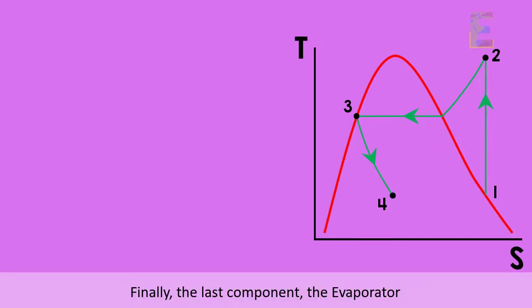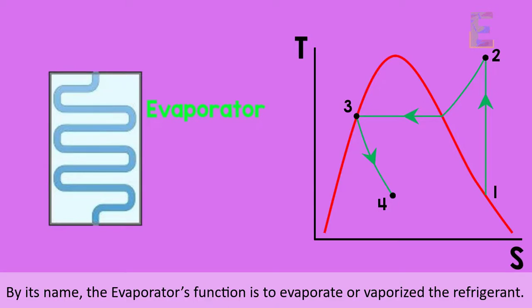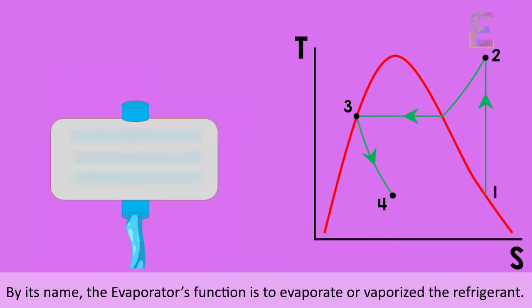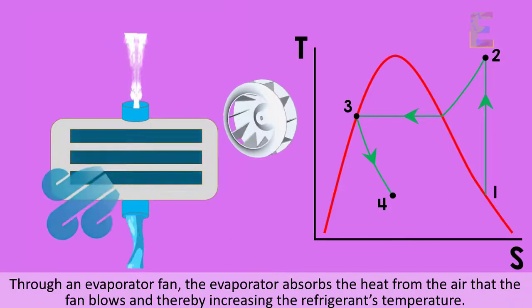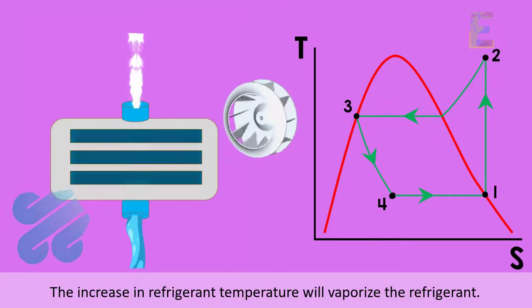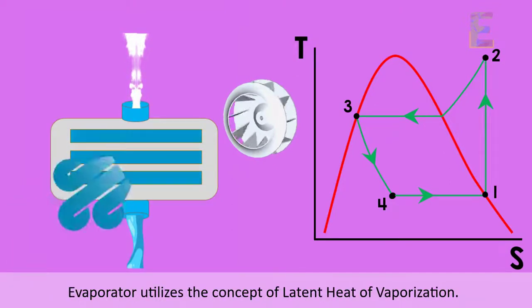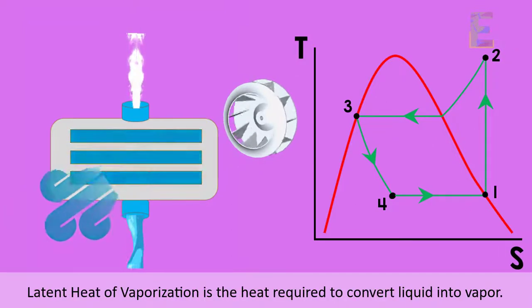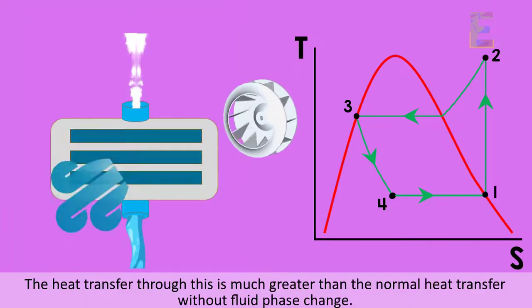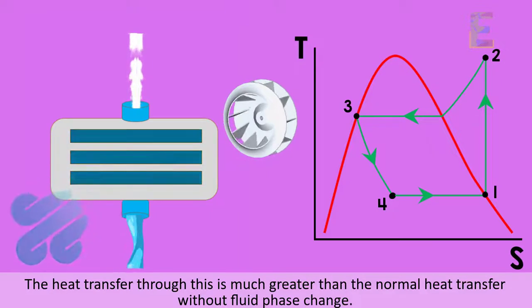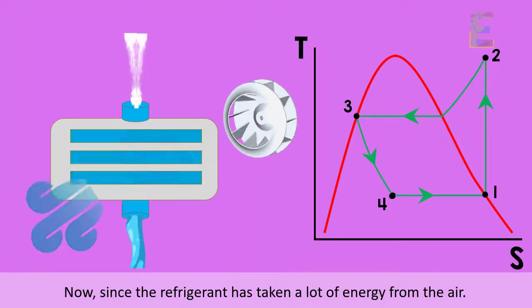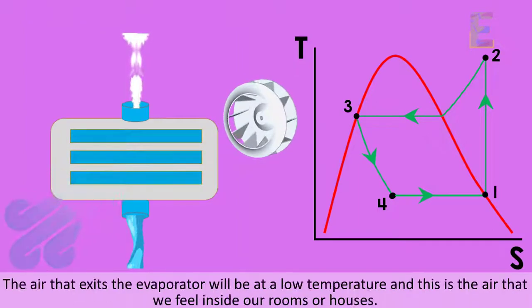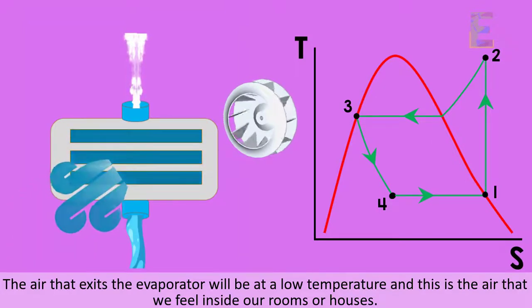Finally, the last component, the evaporator. By its name, the evaporator's function is to evaporate or vaporize the refrigerant. Through an evaporator fan, the evaporator absorbs the heat from the air that the fan blows and thereby increasing the refrigerant's temperature. The increase in refrigerant temperature will vaporize the refrigerant. The evaporator utilizes the concept of latent heat of vaporization. Latent heat of vaporization is the heat required to convert liquid into vapor. The heat transfer through this is much greater than the normal heat transfer without fluid phase change. Now, since the refrigerant has taken a lot of energy from the air, the air that exits the evaporator will be at a low temperature. And this is the air that we feel inside our rooms or houses.